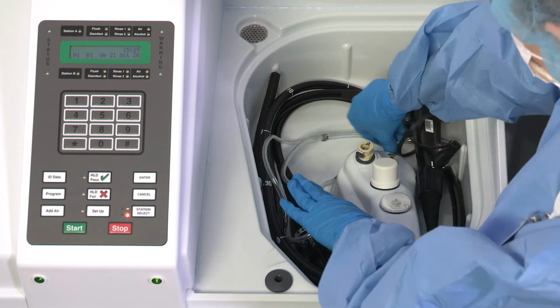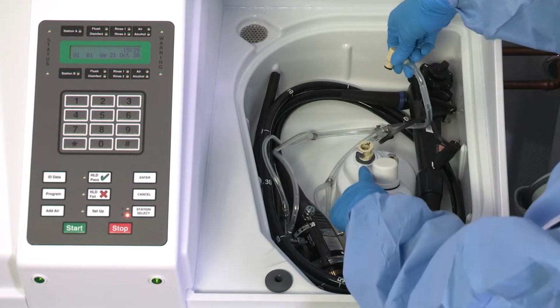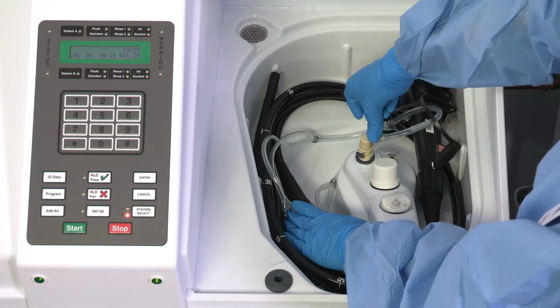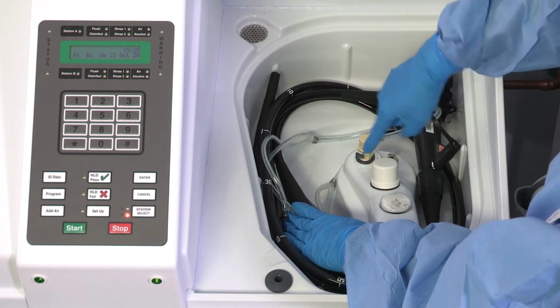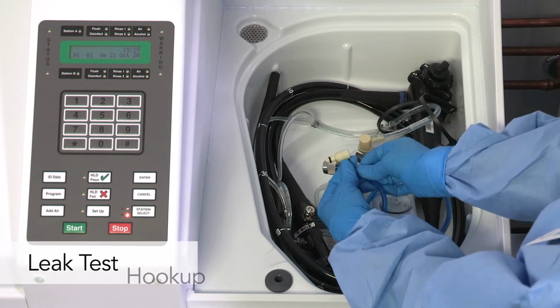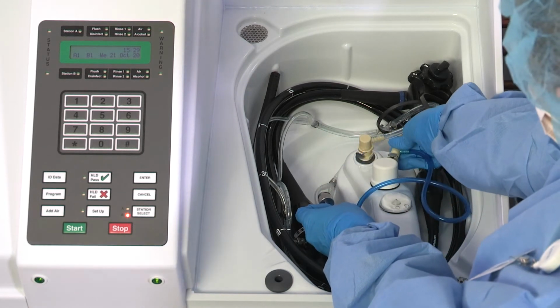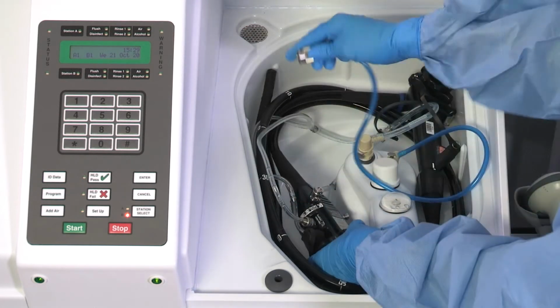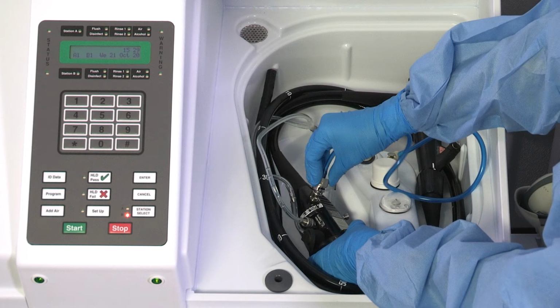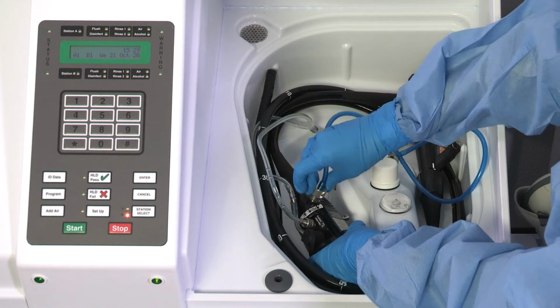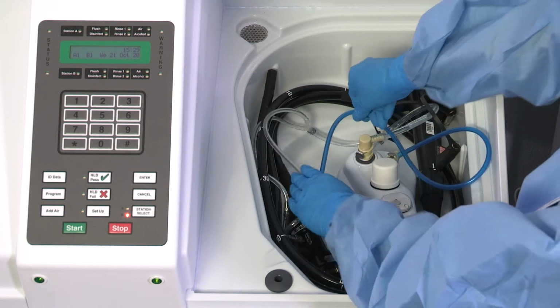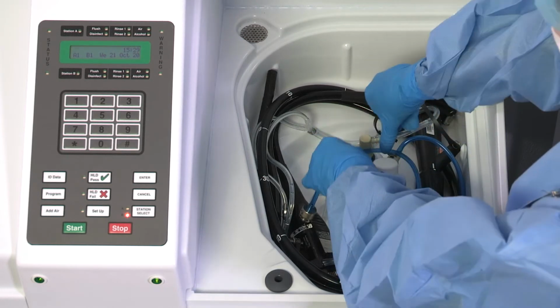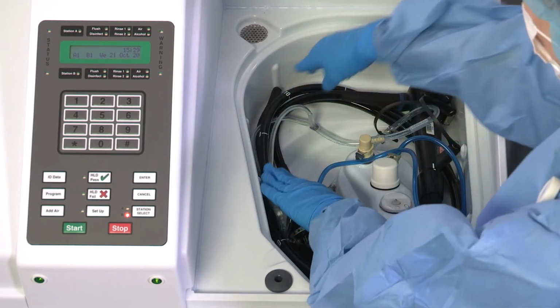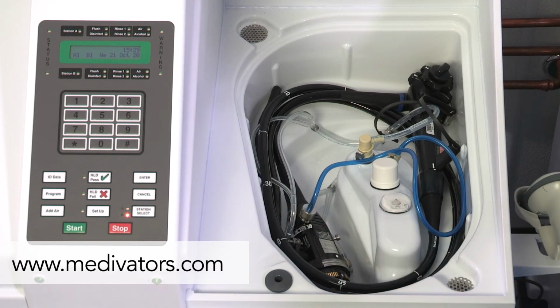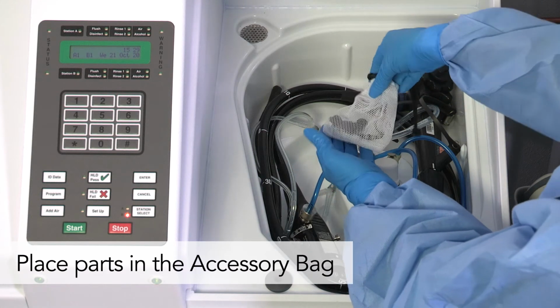Push the basin connector on the end of the DSD hookup into the basin connector port. You will hear a snap and see the metal plate on the basin connector port pop out. To connect the Olympus DSD leak test hookup, connect the hookup to the basin's leak test connector. Align the slot on the hookup with the pin on the endoscope's venting connector. Push on and turn clockwise to engage. To ensure proper connection, refer to the IFUs that are supplied with your hookups or on our website at www.medivators.com. Place loose parts in the accessory bag.